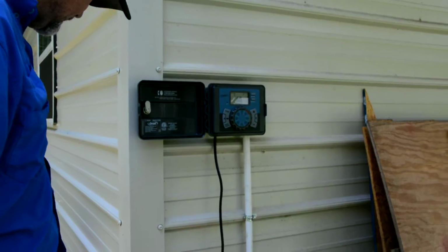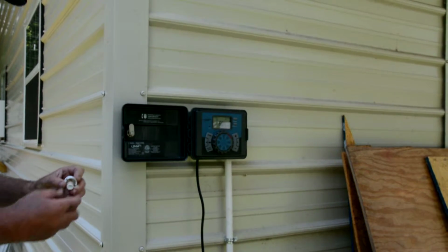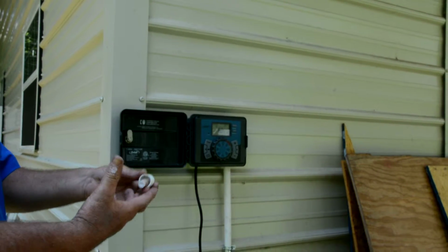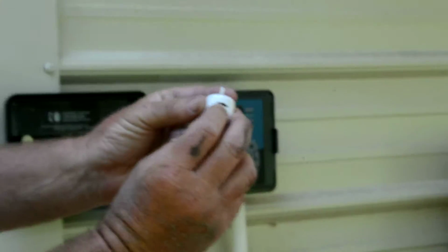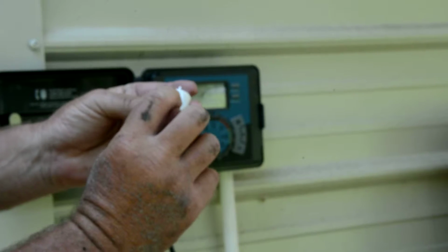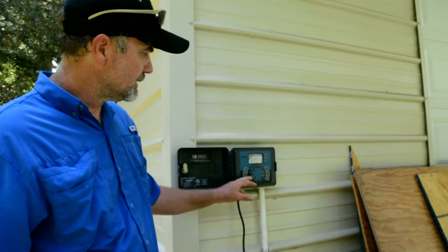This is your rain sensing device. When this gets wet, it has leather washers inside that will swell up, shrink back. These settings here are the settings that we need, 1/8 to 3/4, that will be the sensitivity settings on your system. So at whatever setting we lock it in, I like 1/4 inch of rain to shut her down. And that's the rain sensing part. This will shut the system down when it automatically rains. Or when it rains, it'll shut it down automatically.